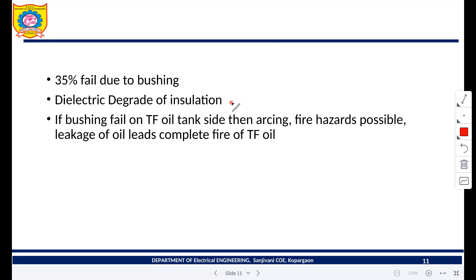If the bushing fails on the transformer oil tank side, the oil is going to leak. Because of this oil leakage, heavy sparking and arcing occur on the transformer tank, and there may be chances of fire hazards. Therefore, the transformer bushing is a very important device for monitoring and testing. 35% of transformer failures are due to the bushing, so care must be taken during installation, and continuous monitoring and testing should be carried out.